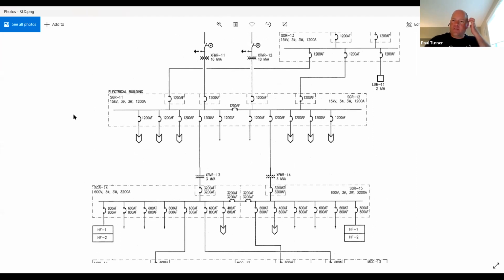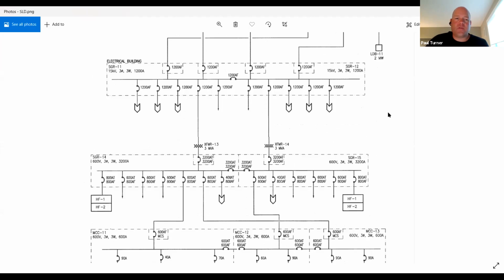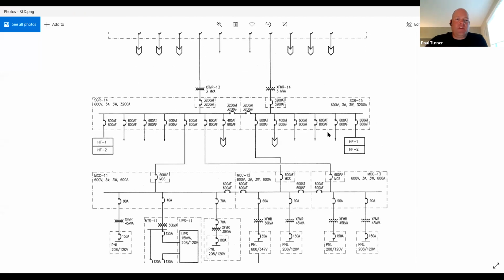That essentially gets the basics of the system up and running to be able to provide power throughout the plant. Then I would probably consider each plant area specific as a separate mechanical completion as well. So the pair of either 15 kV or 600 volt cables from the plant power systems over to the plant area specific MCC and panel board systems as another separate mechanical completion, given that the rest of the plant is likely phased and coming online in various stages. You could split the power to each of those areas as separate mechanical completion, given that power may not be required in one area as early as required in another particular area.